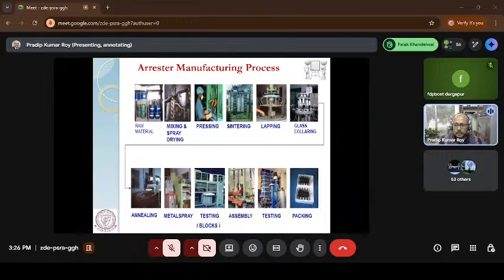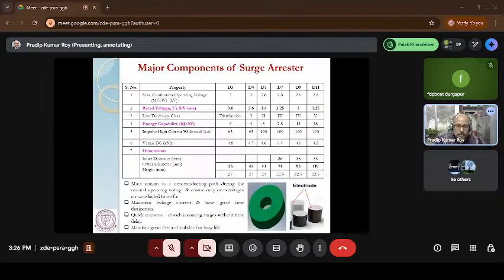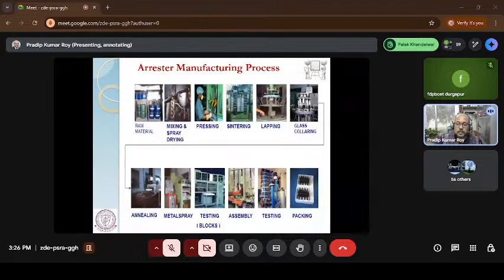Sintering is nothing but a heat treatment method to improve densification. Then they do the lapping. As I mentioned, both surfaces should be parallel, so they do the lapping with silicon carbide abrasive material. During lapping, the bottom plate moves in the clockwise direction and the top plate moves in the anti-clockwise direction. This way, they do the lapping to make the surfaces parallel. Then they do the glass coating around the block. Now, if you look at this figure, the glass coating is given around the block. The purpose is that when the surge comes, there is a chance of what is called the screening effect. All the electrons will go to the edge of the block, and there is a chance of flashover through the side of the block.